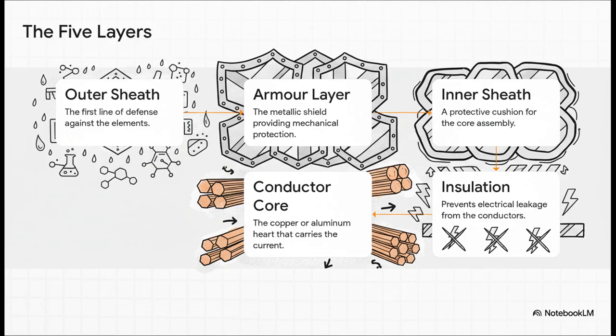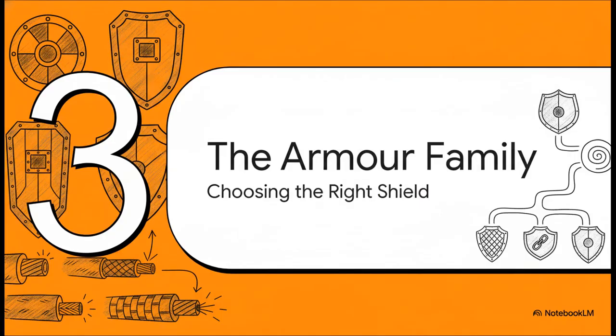Right underneath that is the star of our show, the armor layer itself. We'll get more into that in a second. Nestled inside the armor is the inner sheath, which is also called the bedding. It's basically a protective cushion. Then we get to the insulation, often made of a super tough material called cross-linked polyethylene, or XLPE. Its job is to keep all that electricity from leaking out. And finally, right at the very heart of it all, is the conductor core, the copper or aluminum superhighway that's actually carrying the power.